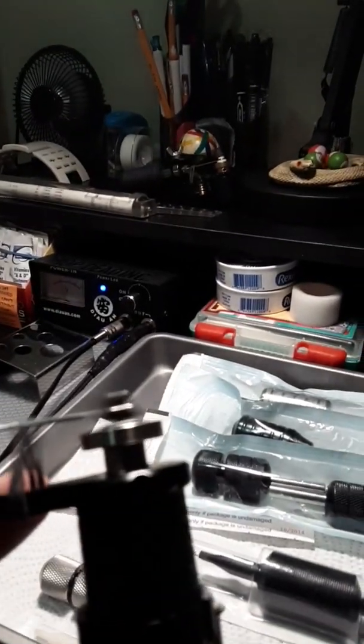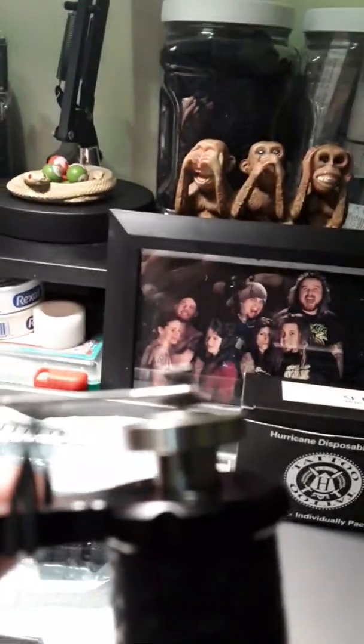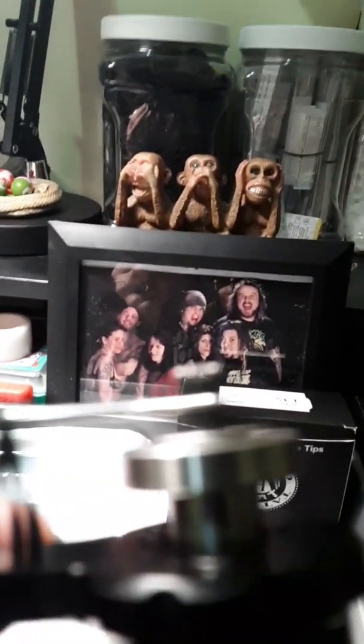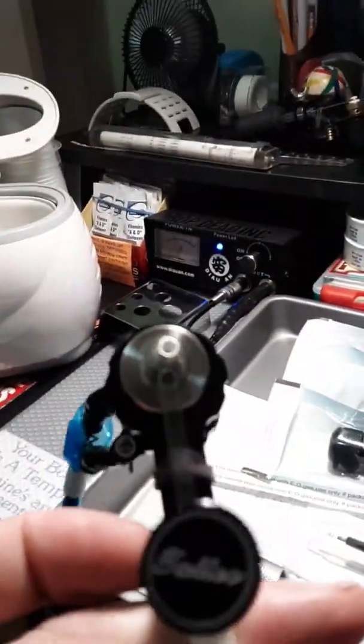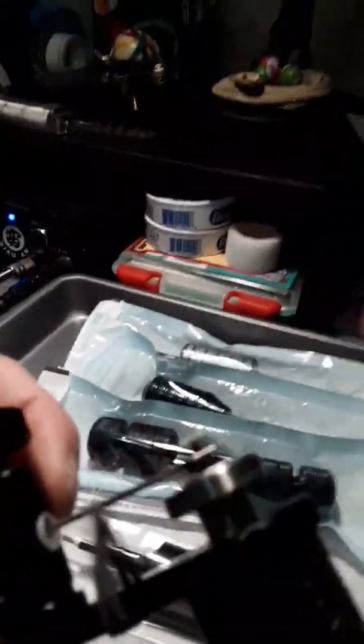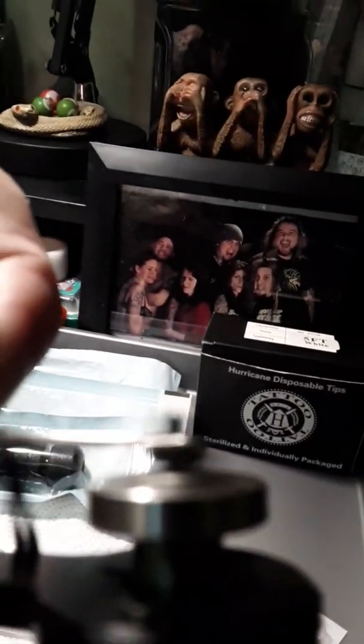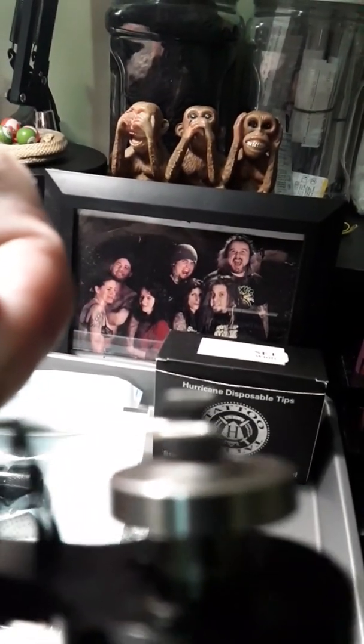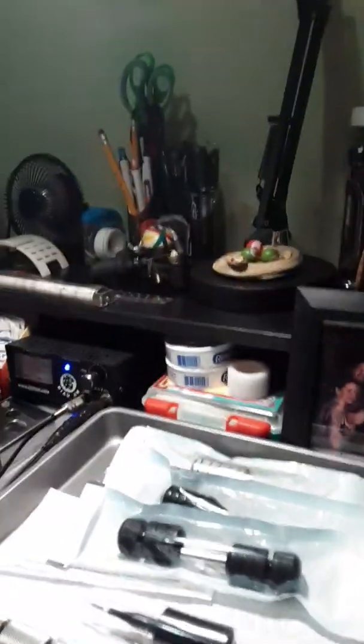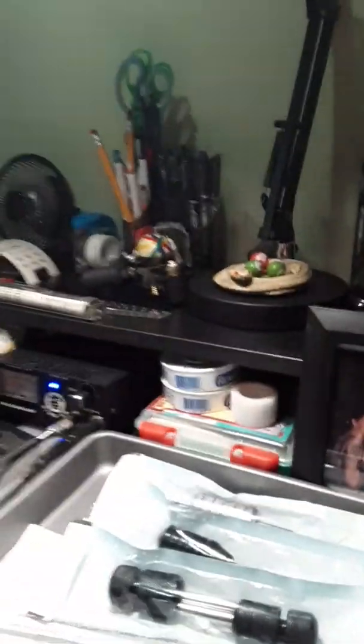And again, that's 4 millimeter, and you can probably see right there that little gap in that armature bar is probably about a nickel. See if I can capture it better. Maybe not, but you can kind of see it from the side. So that's the gap you're looking for when that armature bar is moving back and forth. It should be about a nickel width, which I'm sure it is, and that's a 4 millimeter. That's what it's set on.